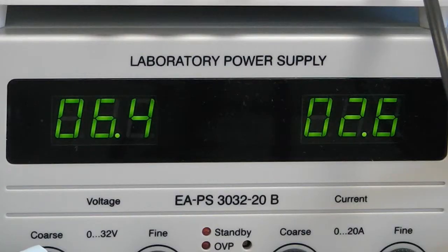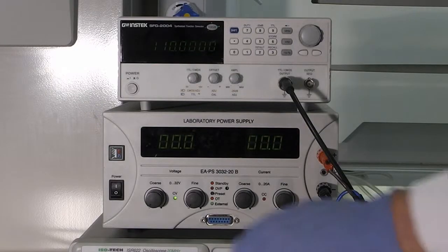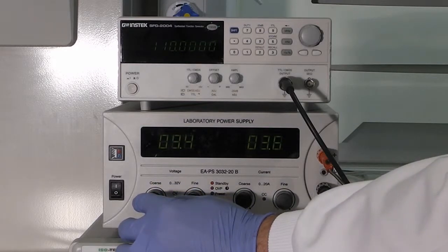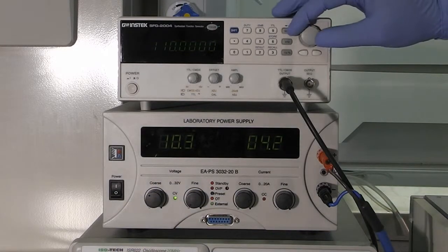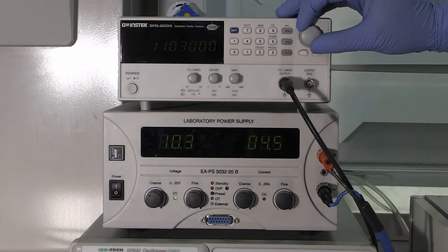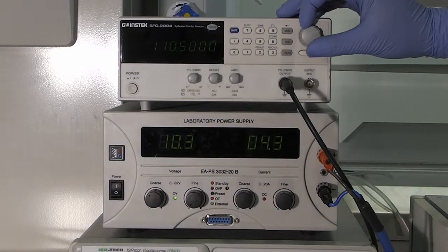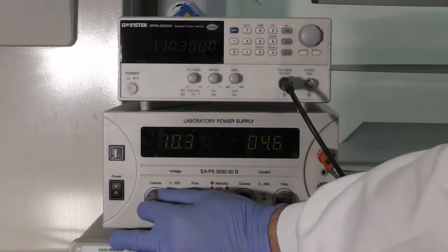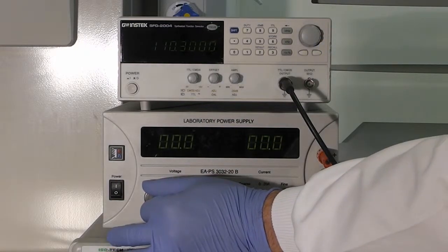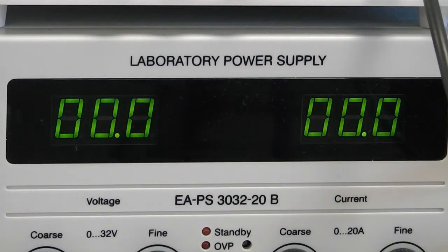Take 1/3 of the voltage input for 110 kHz from the matrix sheet, 10 volts. Now slowly increase the voltage to 10 volts and you will observe a peak-to-peak voltage increase in the oscilloscope signal. Now tune the circuit to its resonant frequency, i.e. the frequency at which the current is highest within the circuit. When this tuning is done, lower the voltage back to 0.